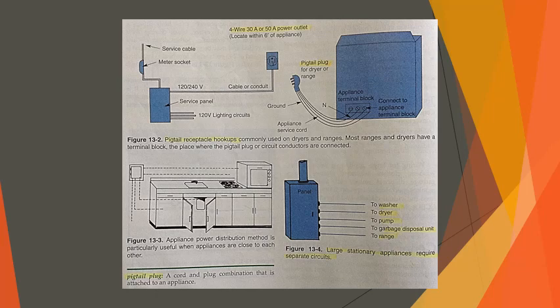Appliances should be placed on a separate circuit if, as in the case of washers, dryers, ranges, garbage disposals, dishwashers, pumps, motors, and the like, they are rated above 12 amperes or 1/8 horsepower or 240 volts. See figure 13-4. Appliance classification. Article 550 of the NEC separates appliances into three types: fixed, portable, and stationary. Since this article covers mobile homes, these definitions do not apply anywhere else in the NEC, although it may be helpful to read and understand Article 550. Refer to Article 422 for most appliance issues.